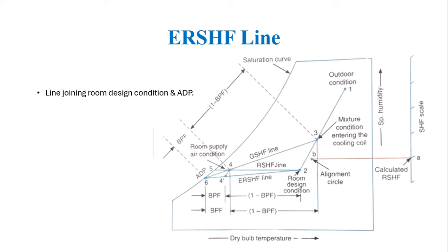The combined diagram shows all three lines: the RSHF line joining room design condition and supply air condition, the GSHF line joining mixed condition and supply air condition, and the ERSHF line joining ADP and room design condition. Process 3 to 4 is the cooling process, and the line from 4 to 6 represents the inefficiency of the coil — the bypass factor — while the remaining length is 1 minus the bypass factor. These are the key terms in psychrometry and air conditioning used for solving numerical problems.